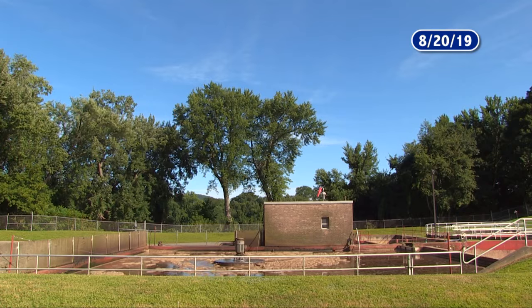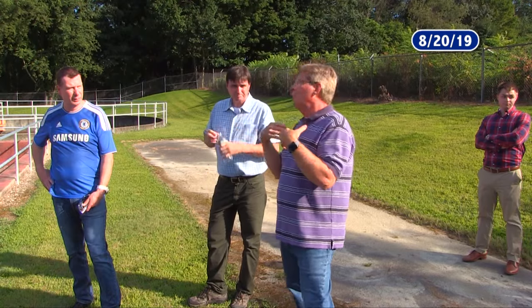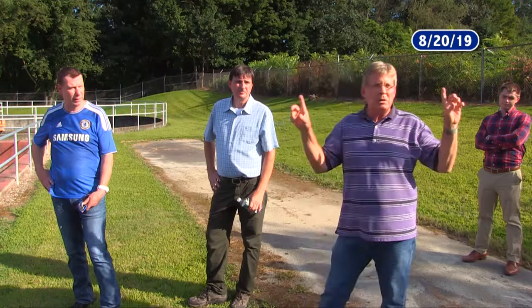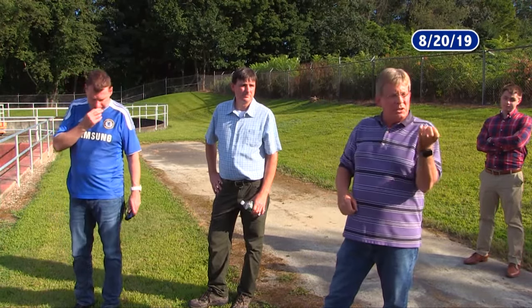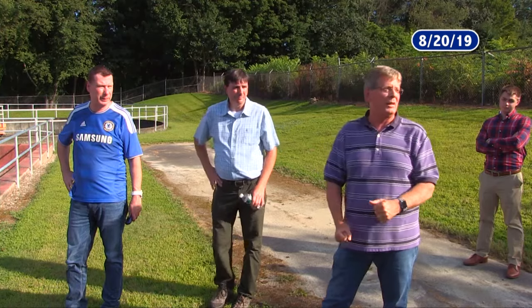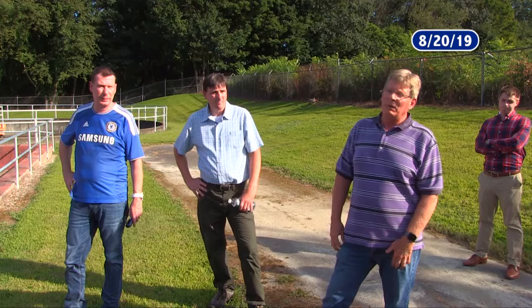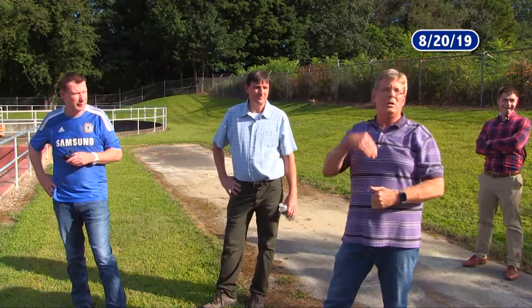And we have to maintain a certain average for removal of suspended solids and pollution, which I refer to as BOD. I know you guys hear me saying BOD. Biochemical oxygen demand. It's just a way to measure the relative strength of the waste coming in. How that's done is how fast it depletes oxygen in a bottle over 5 days. So we run this test every week for regulatory purposes. And we have permit parameters that tell us if you're over this value for the month, you're in violation, etc.